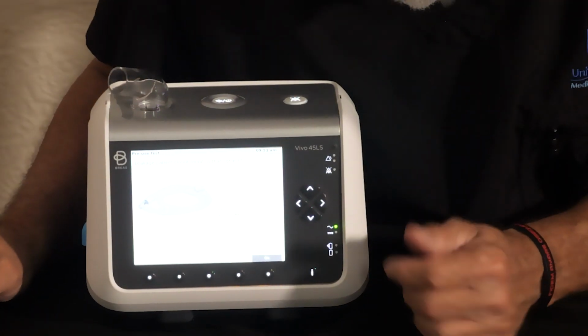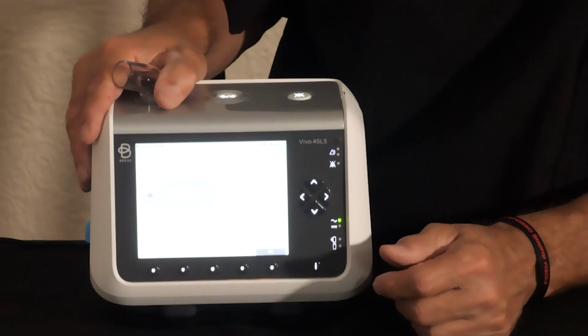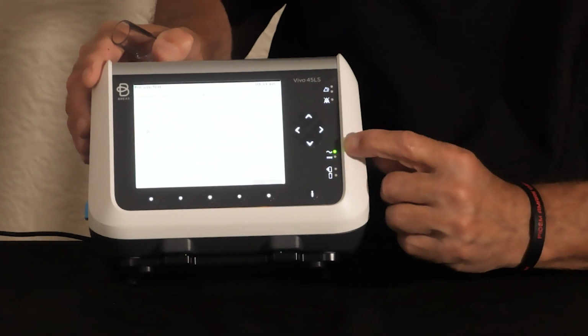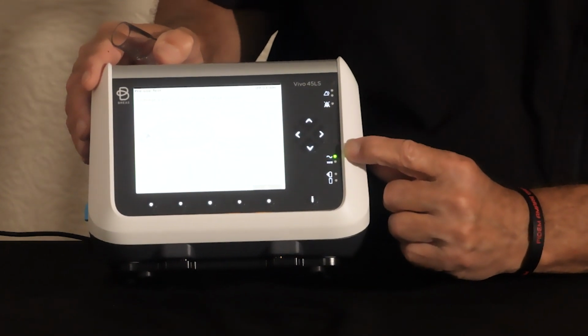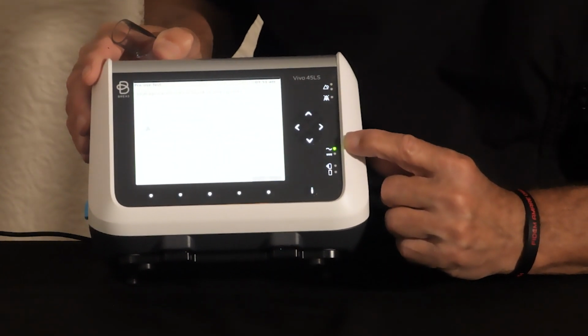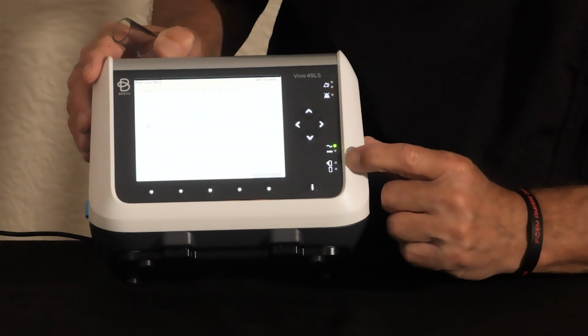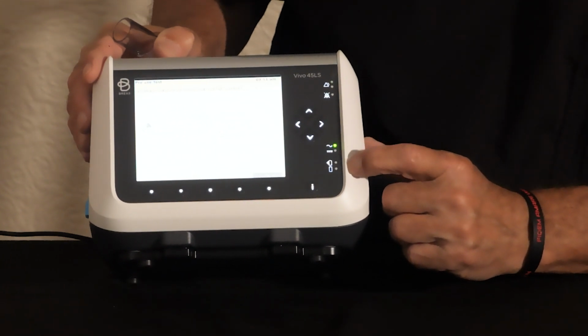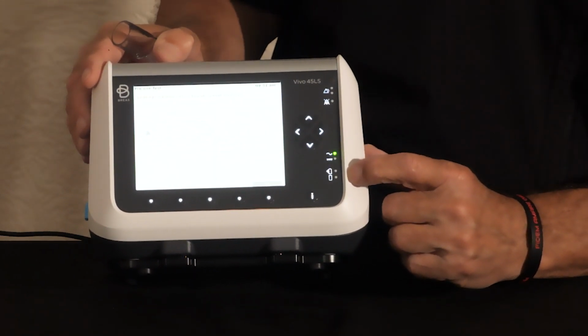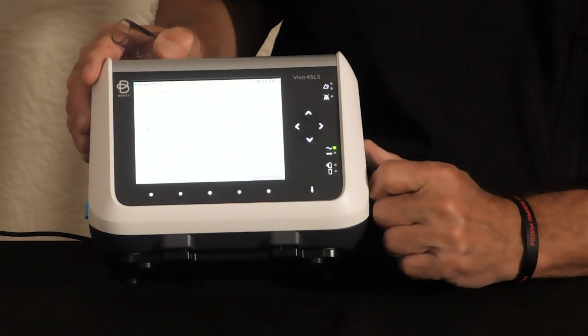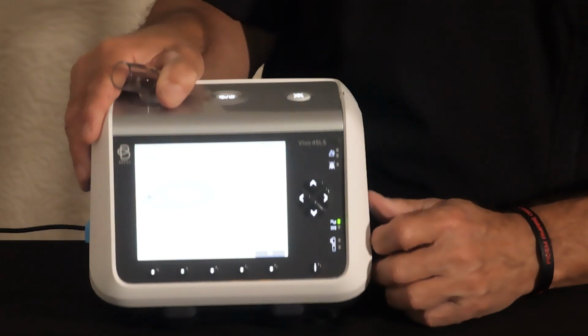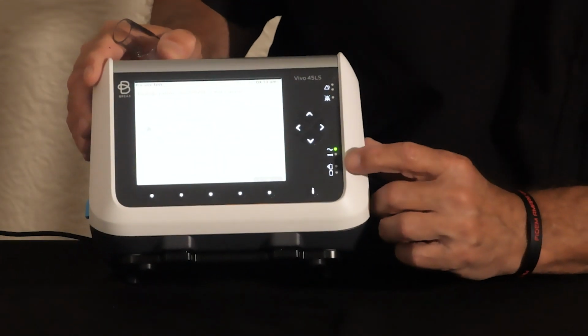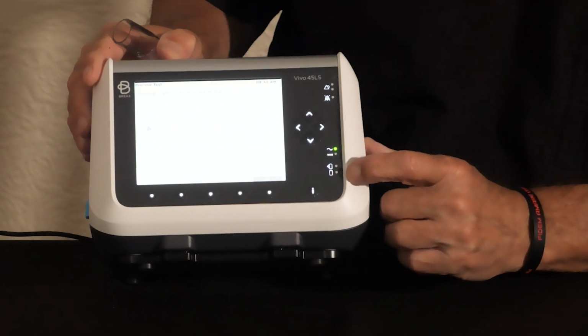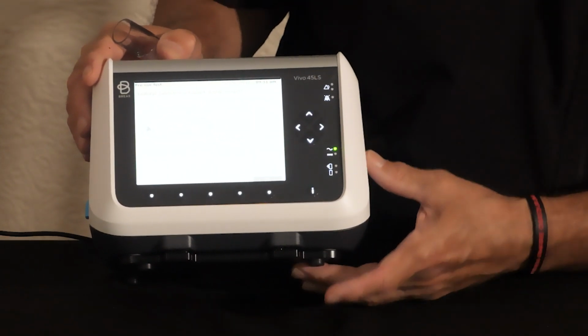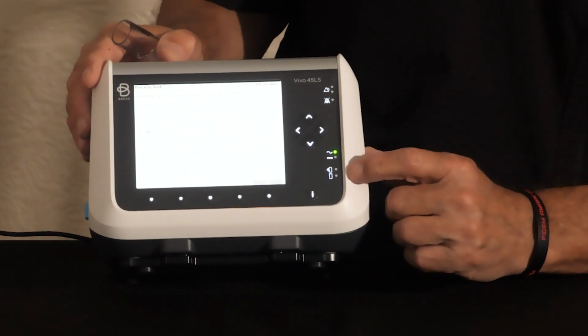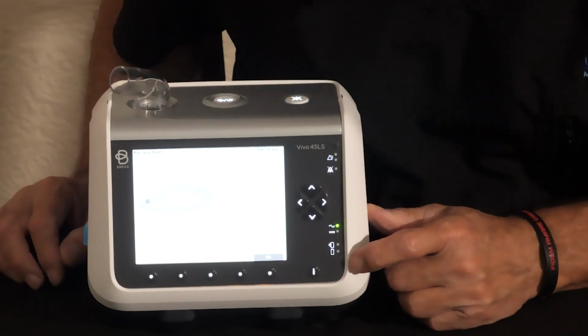All right, if you look at the very front of the ventilator here, you're going to have some lights. This top light here means that it's actually plugged in. So the wavy line means that it's plugged in. You have 2 battery indicators here. They're also lit up when the batteries are in use. The one with the little arrow pointing to the side, that's your detachable battery. That's your 6.5 hour battery source. And the one below is your internal battery, and that is 2.5 hours for a total of 9 hours approximate battery life.